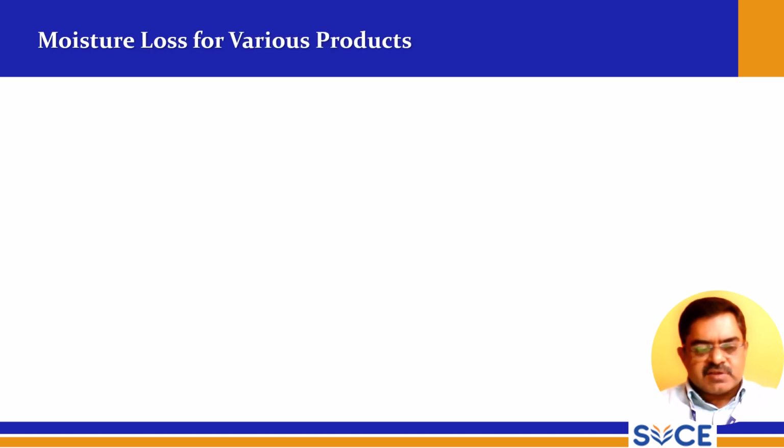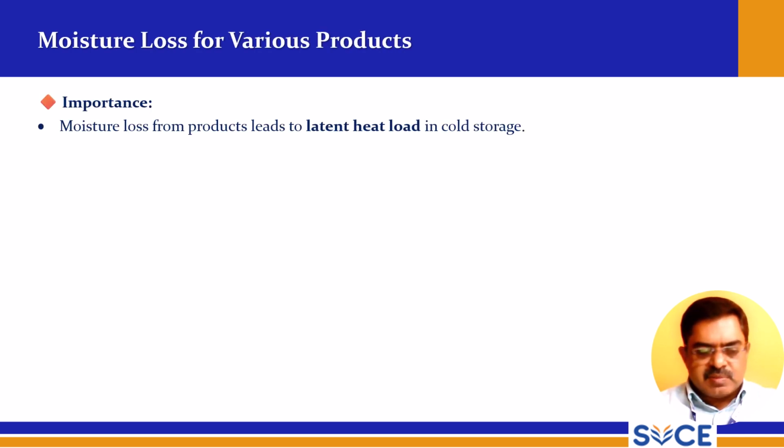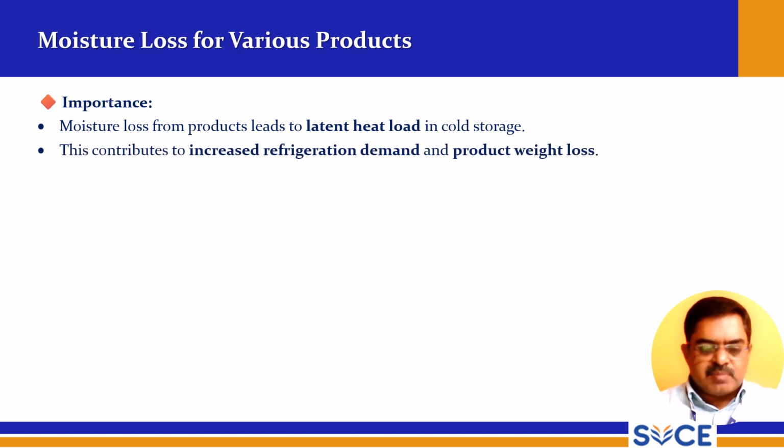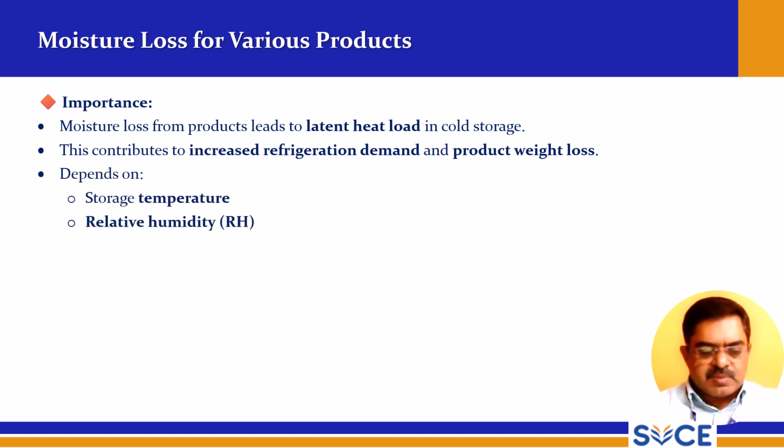So moisture losses for various products are very important, since moisture loss from products leads to latent heat load in cold storage. So there will be a rise in moisture, and this contributes to increased refrigeration demand and product weight loss. It depends on storage temperature, relative humidity, storage duration, and the nature of the product.